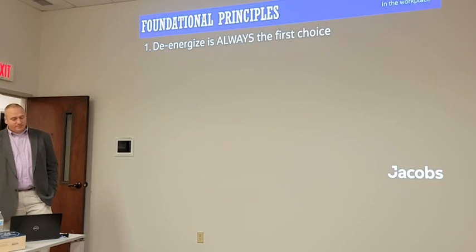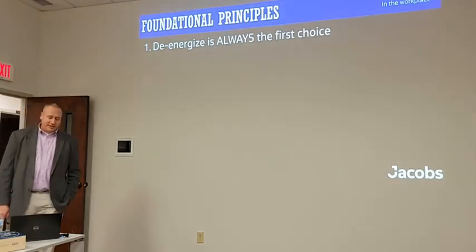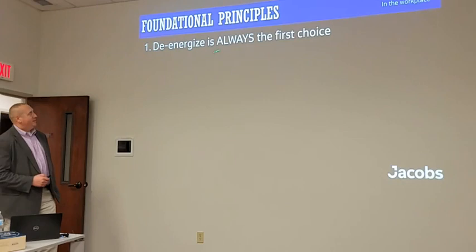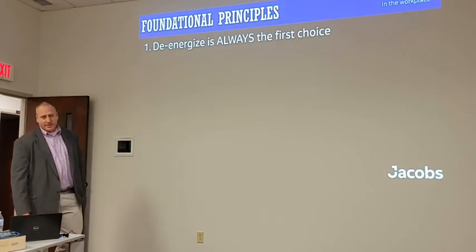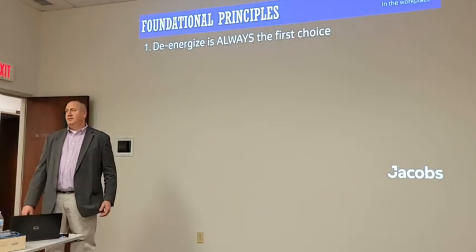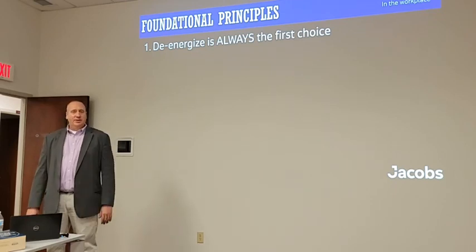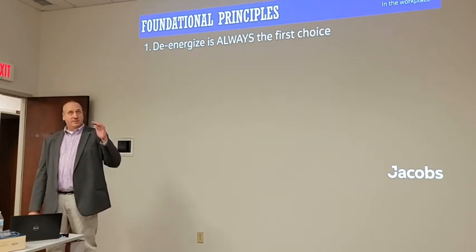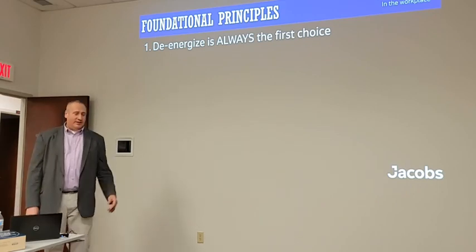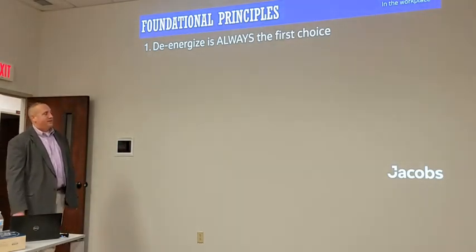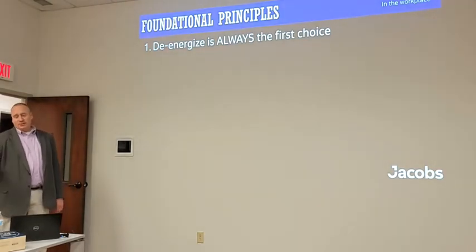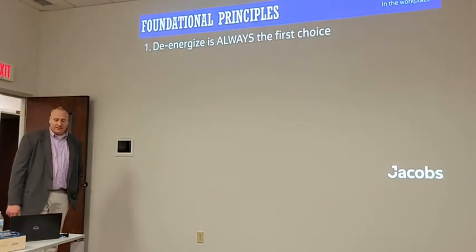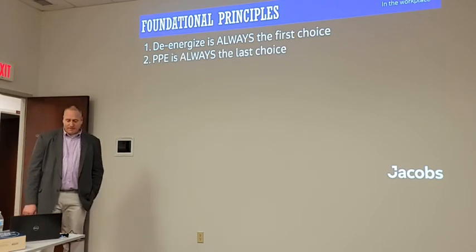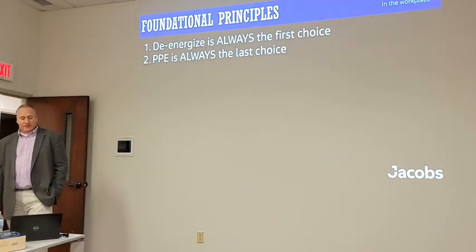In closing, some foundational principles. De-energizing is always the first choice, and really, de-energizing is a bad term. It's really electrically safe work condition, which is an NFPA 70E requirement that has several different steps to get to that, not just de-energized, it's locked out, tagged out. You verify, visually verify, that it's open. You can do a live-dead-live method to make sure that it's de-energized. You go through all these steps, ground it if it's feasible to ground it, then it's safe to work on. PPE is always the last choice.